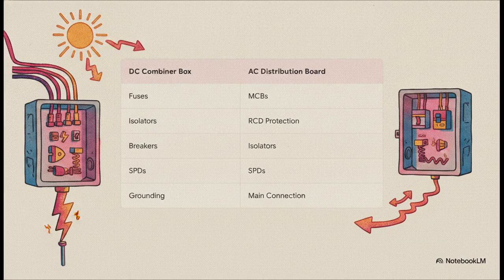But a solar system actually requires two totally different layers of protection. First up is the DC combiner box. In our animation, we see these cables traveling from the roof straight into this 3D box. Because this energy is raw, direct current coming directly from the sun, it houses specialized gear: DC fuses, isolators, breakers, and surge protection devices, or SPDs, to guard against things like lightning strikes, plus proper grounding. We'll deal with the AC side of the house in just a second.